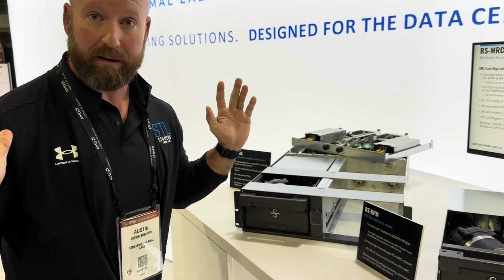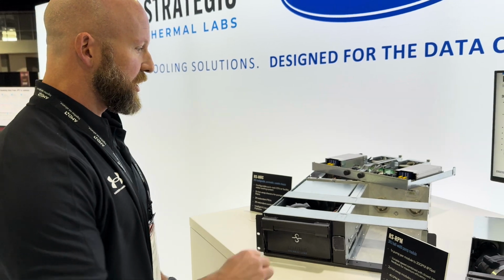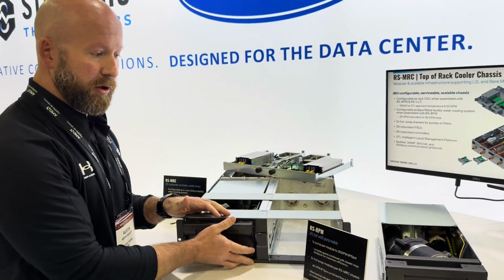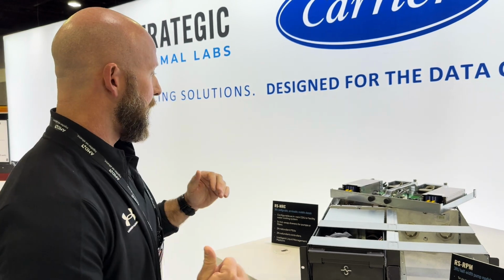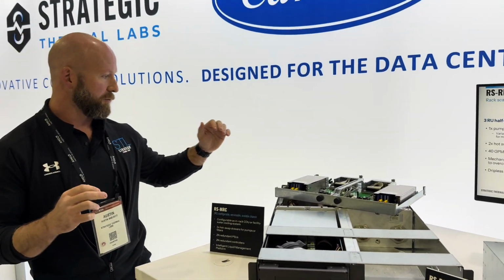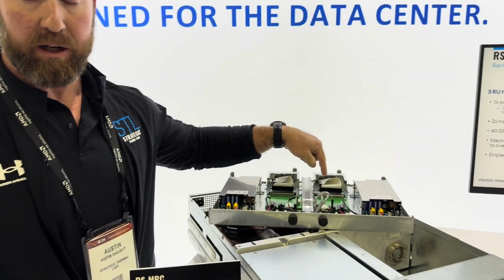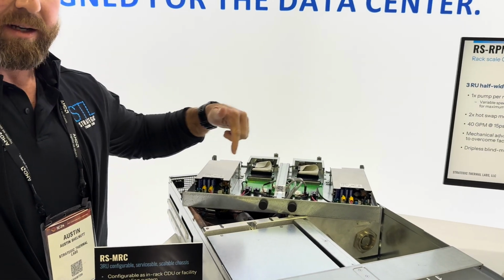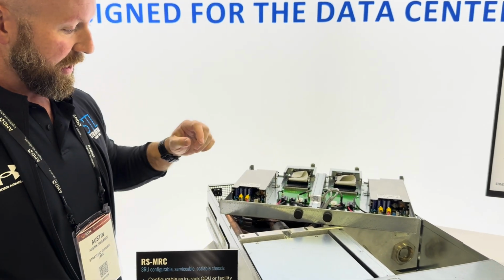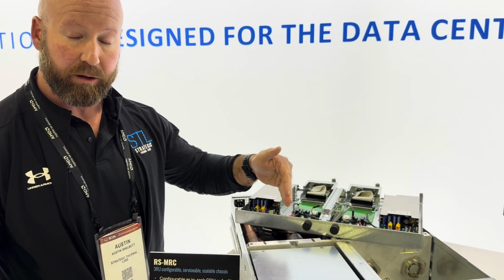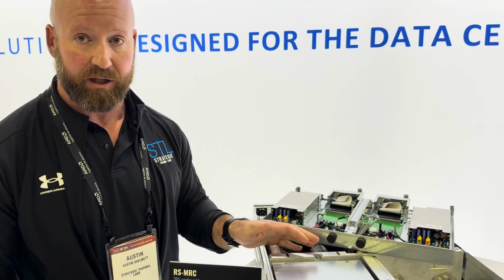And just like that, the new pump is installed. The chassis that these move into is called the MRC, or Modular Rack Cooling Device. Follow me back here. We've got hot swappable redundant controllers. We've got redundant DC power supplies. And then we have integrated differential pressure, flow meters, and leak sense in the back of the chassis as well.